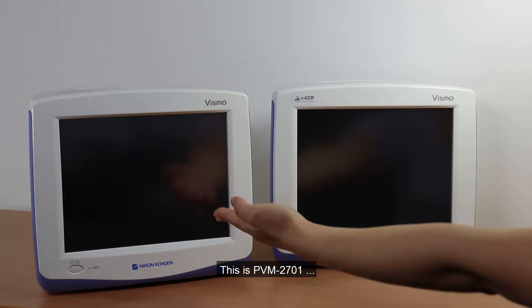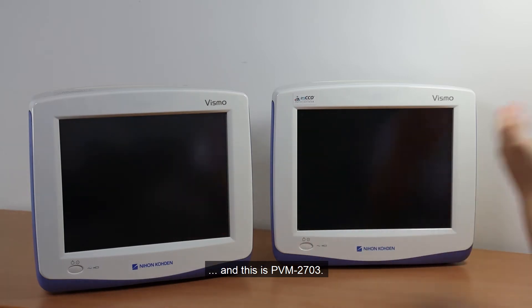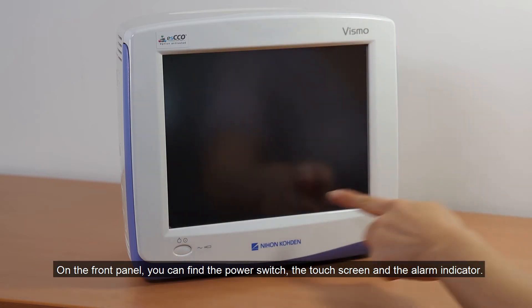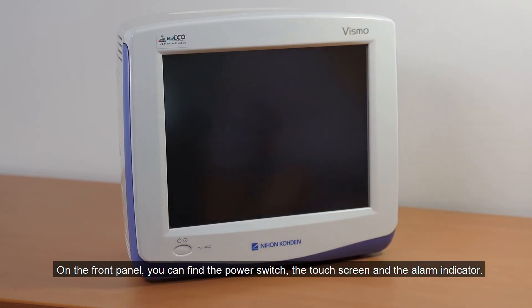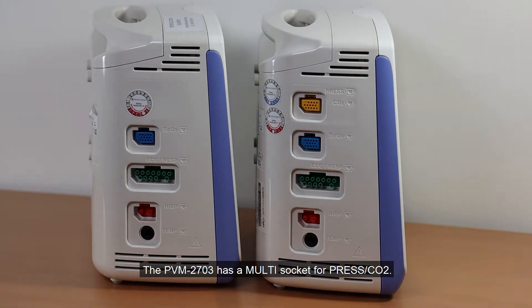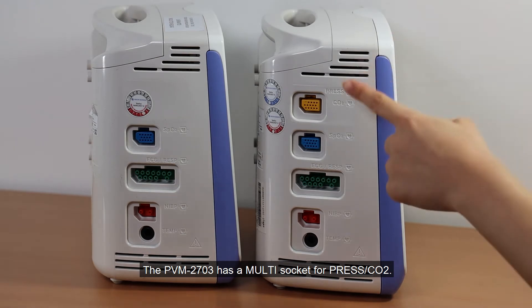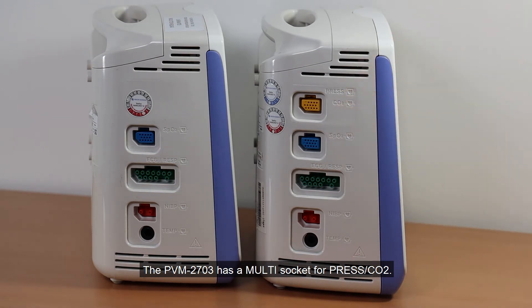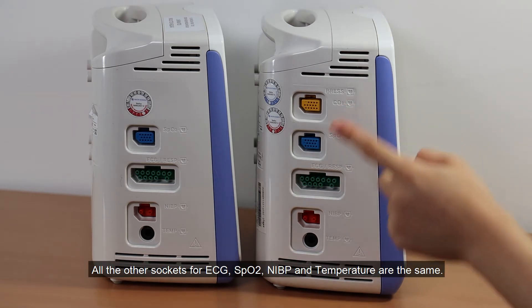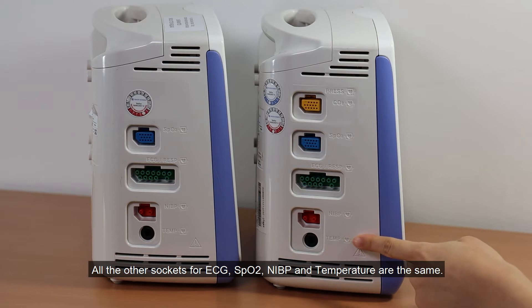This is PVM-2701 and this is PVM-2703. On the front panel, you can find the power switch, the touch screen, and the alarm indicator. The external difference between the two models is the left side panel. The PVM-2703 has a multi-socket for IBP and CO2. All the other sockets for ECG, SpO2, NIBP, and temperature are the same.